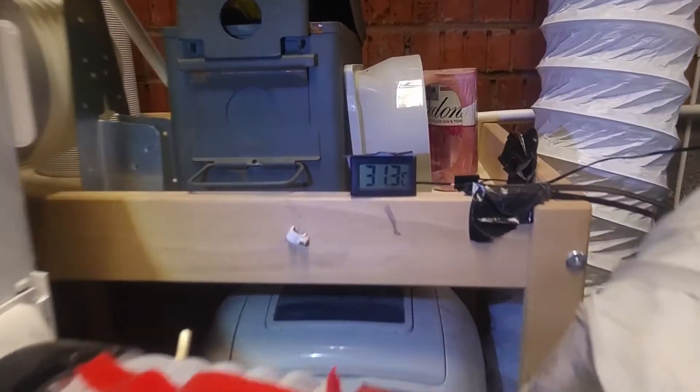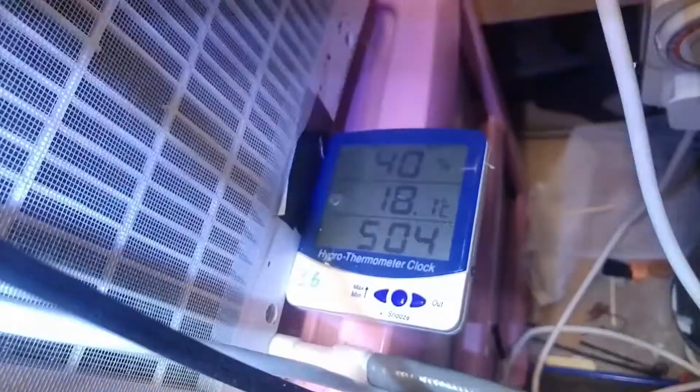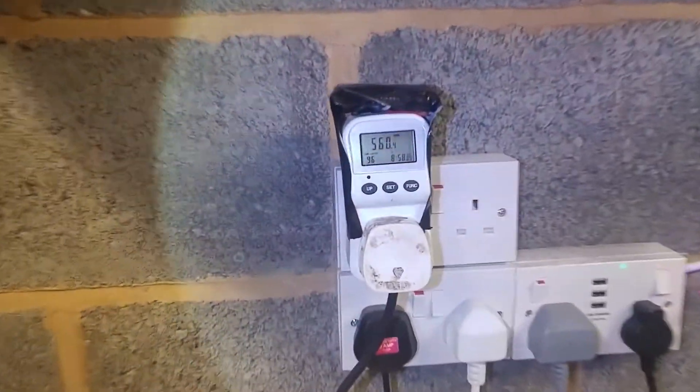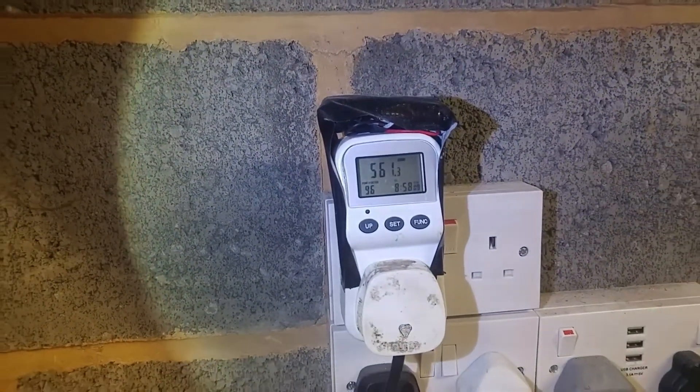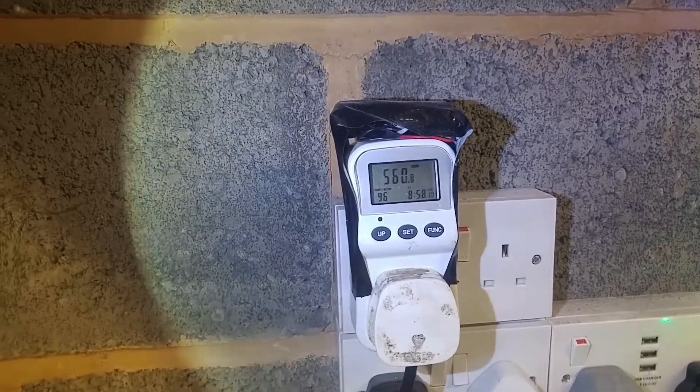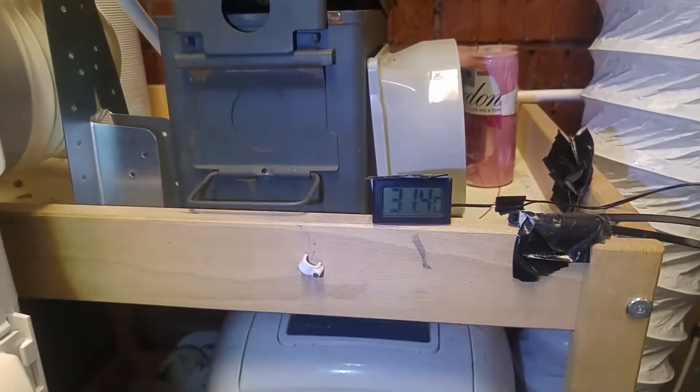So it's leveled out now at about 31.3 on the outlet and 18 on the inlet. And the power is half a kilowatt. So you can already see that it's using half the energy of the fan heater and making more heat with the same air flow. And that's where the free energy is coming from.